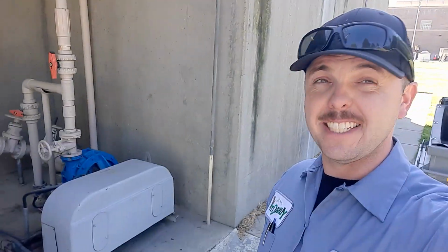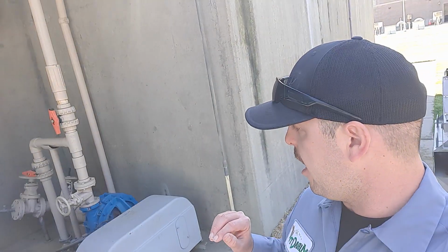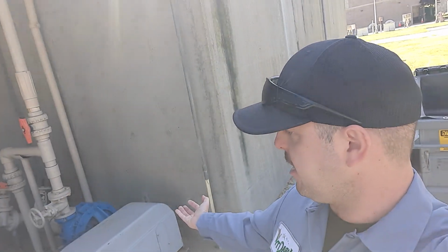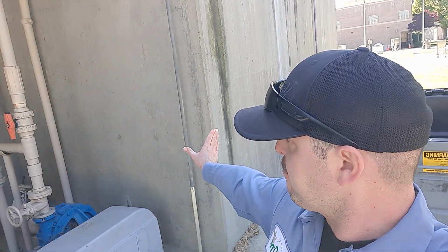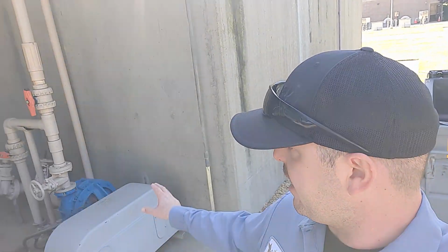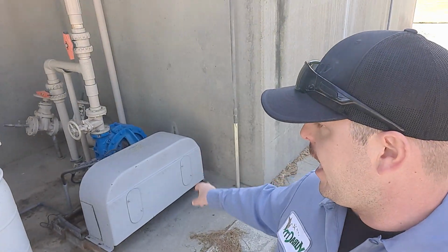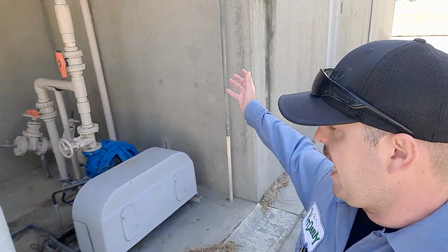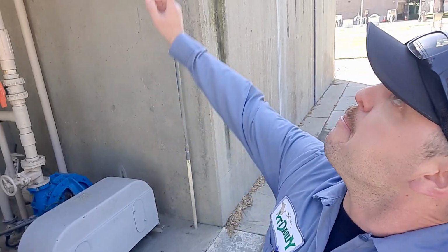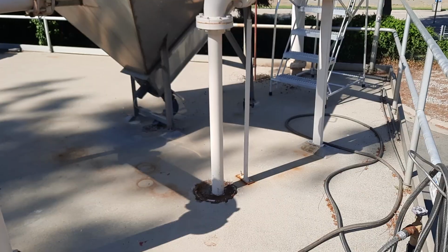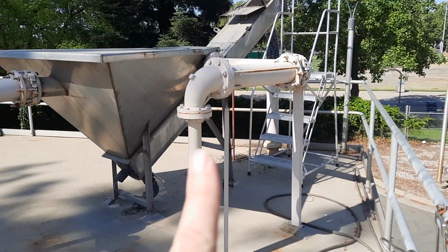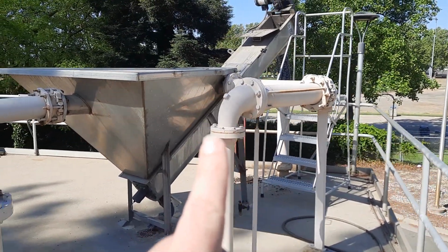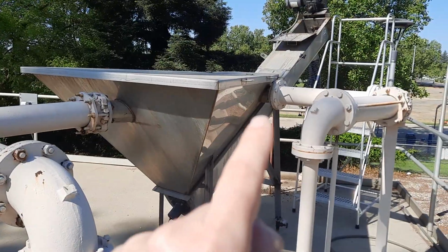So here I am at the bottom of the grit basin. See, it's kind of a tall structure, so after all the air causes the grit to, in theory, fall out, there's a V-notch at the bottom of this area right here. And basically, that pump you're looking at right there will periodically turn on, and it's just going to suck all that grit out and pump it up to the grit classifier upstairs. Here you can see that pipe. That's where the grit is pumped up into this grit classifier.